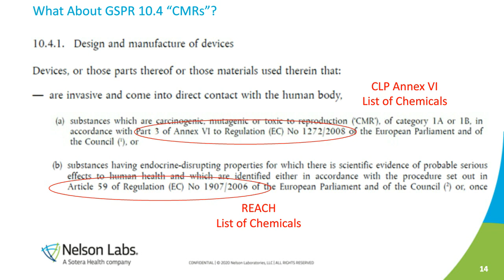And the intention of this, as far as we've understood from our conversations with notified bodies, is that the medical device manufacturers should be asking their suppliers for this information up front, and the suppliers are really supposed to be ready and able to give this to their customers. And at first, a lot of the conversation was that yes, we've asked our suppliers, and they say that the formulation is confidential, and they just won't tell us whether or not there's any CMRs above 0.1%. We heard that a lot, but now over time we've been seeing more and more suppliers willing to make these CMR statements or certificates where they simply claim, no, there aren't any chemicals on this CLP Annex 6 CMR list that are present above 0.1% by weight.